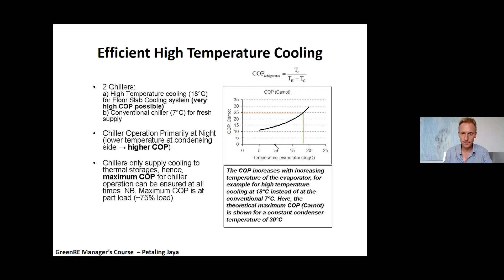Now you're delivering 18-degree water, and you can see the COP, which is the coefficient of performance, the efficiency of the chiller, actually increases a lot. This is the theoretical max. We can't achieve this kind of performance, but we can definitely get something like double the efficiency of the chiller. And we've shown this for other projects as well.